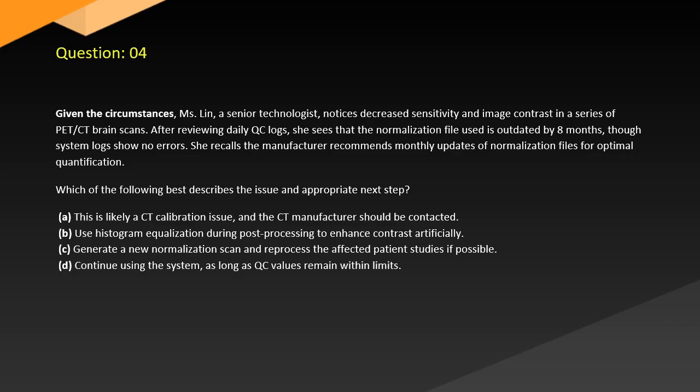Question 4. Given the circumstances, Lynn, a senior technologist, notices decreased sensitivity and image contrast in a series of PET brain scans. After reviewing daily QC logs, she sees that the normalization file used is outdated by 8 months, though system logs show no errors. She recalls the manufacturer recommends monthly updates of normalization files for optimal quantification. Which of the following best describes the issue and appropriate next step?